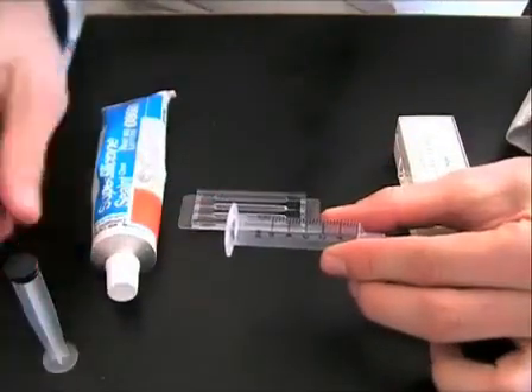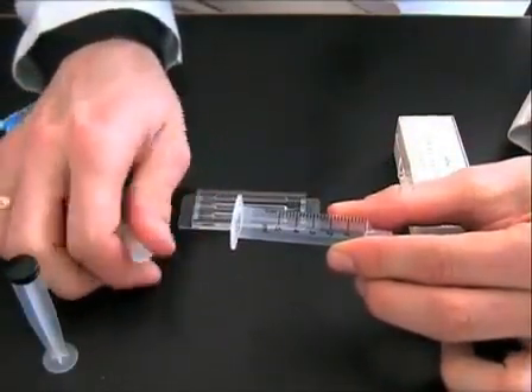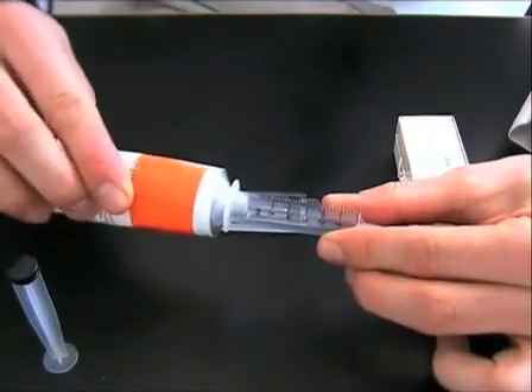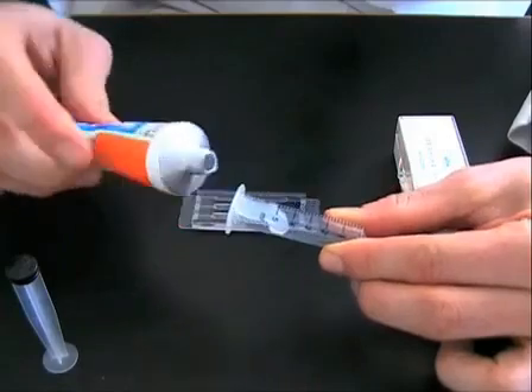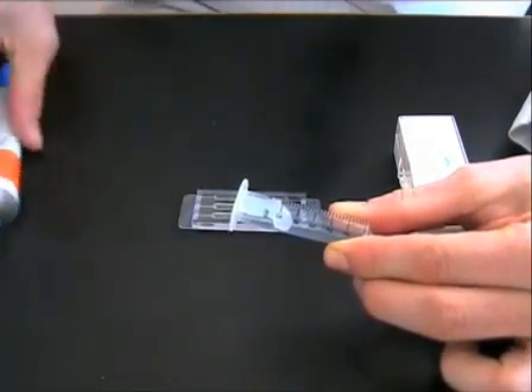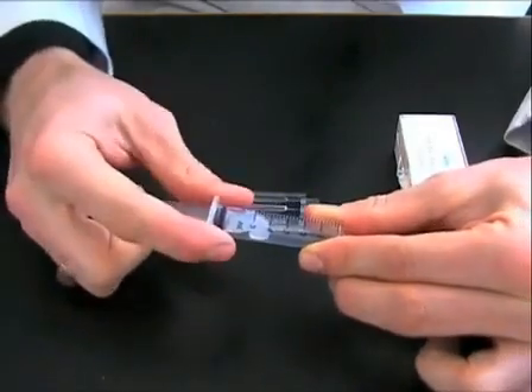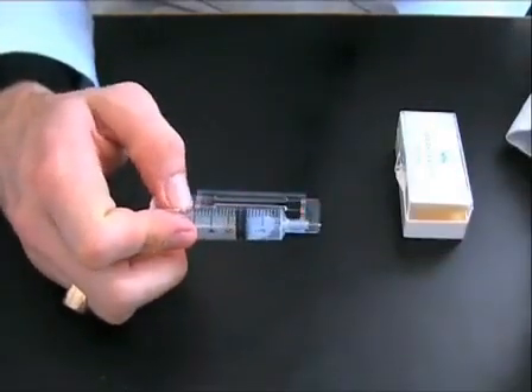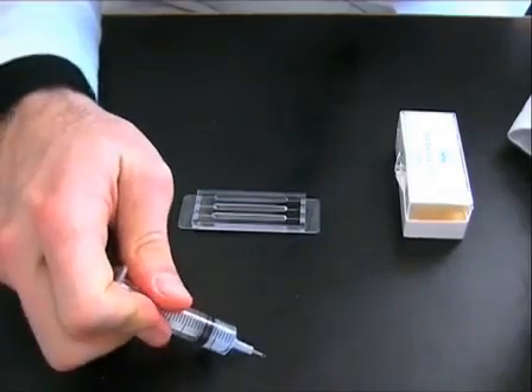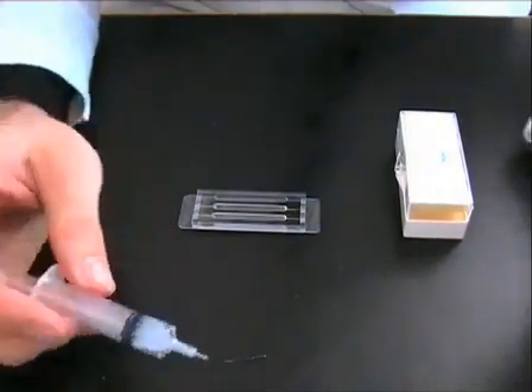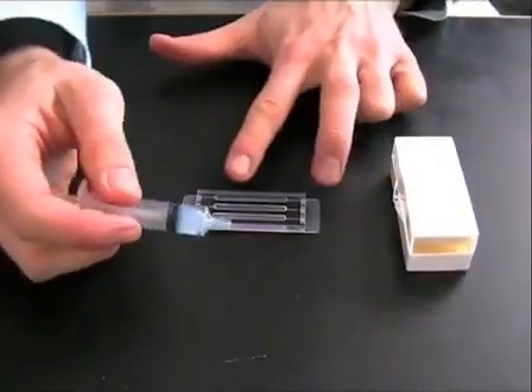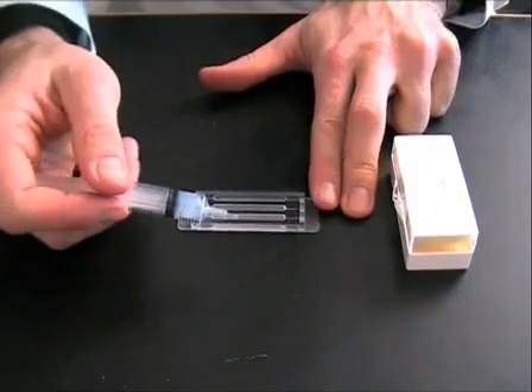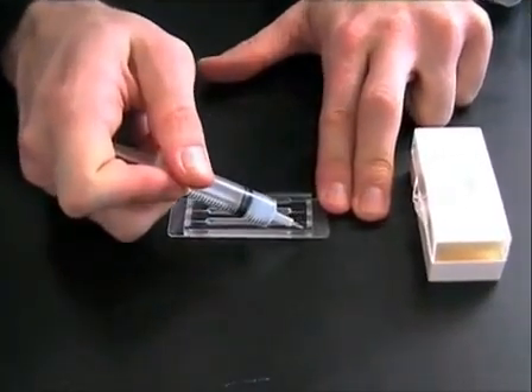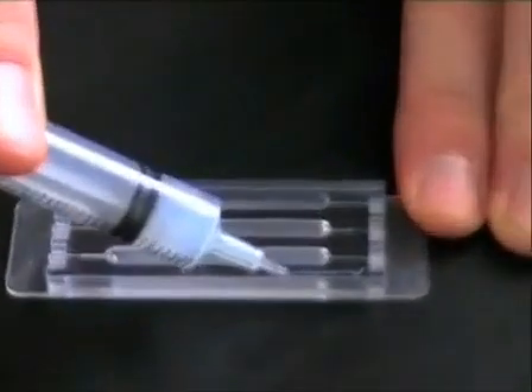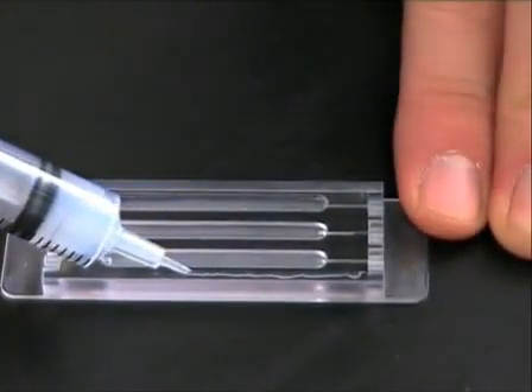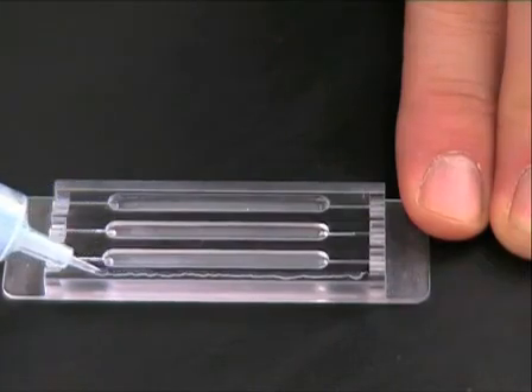Take out the piston and apply an appropriate amount of silicone into the syringe. Put the piston back into the syringe and push a little bit of silicone out in order to make sure that all the bubbles are gone. Now start applying thin lines of silicone to the flow cell. Try and make smooth and non-disrupted lines of silicone to the flow cell. This will ensure that the silicone will attach evenly to the substratum.